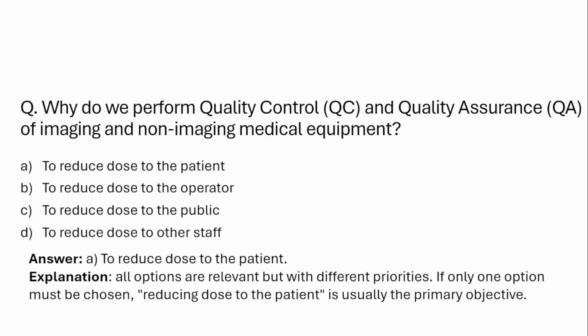So the basic reason behind performing QC and QA of imaging or non-imaging medical equipment. Here in this question, all options are relevant, but with respect to different priorities. If only one option must be chosen, we will choose to reduce dose to patient. That is our primary objective.